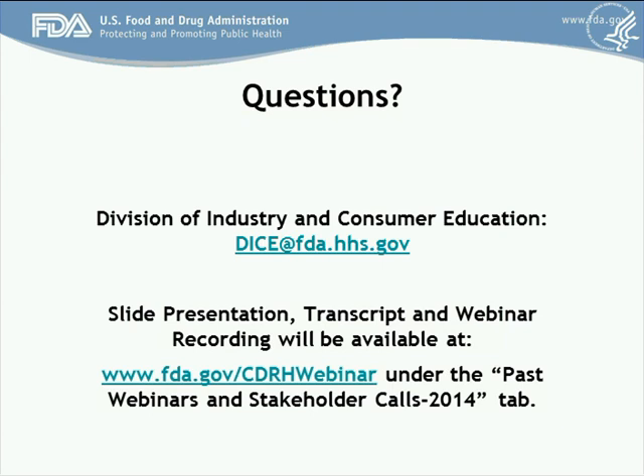To your first point, this would be in your software risk analysis section. So the cybersecurity risk analysis would ask you to do would be called out specifically, but would be part of your software submission. In terms of your second question, could you repeat that? I'm not sure I fully grasped what you were asking. So since we've never provided this information before in our 510K submissions, if I have an update that would require a special 510K, we would actually have to essentially baseline all the requirements of this guidance at that point in time. Is that correct? So when we submit a special now, we submit based on any new information. So since we've never submitted this information before, we would have to submit it at that point in time, yes, even though the change isn't necessarily related to cybersecurity. Yes. At least the cybersecurity section of your risk analysis would have to be complete. Okay. Thank you.